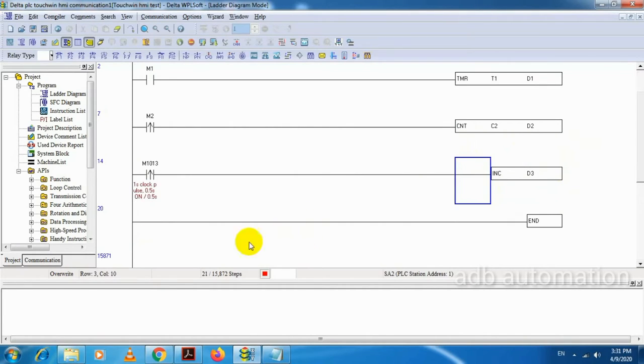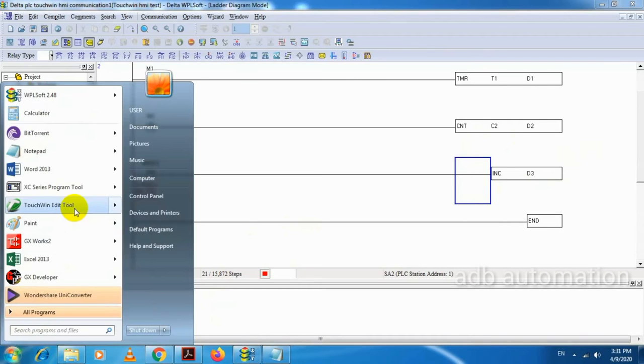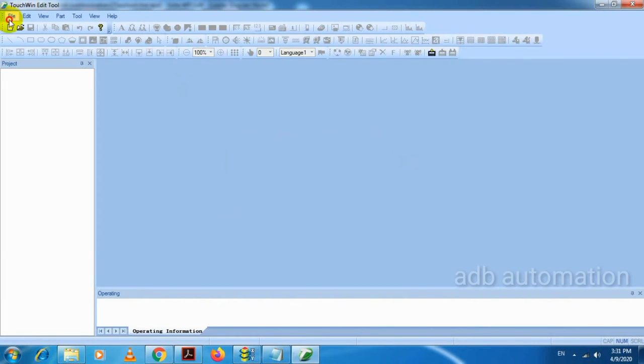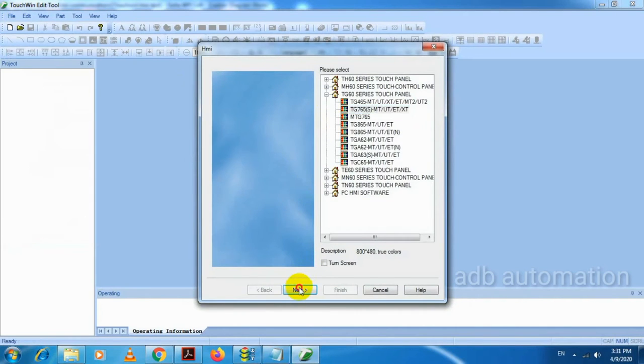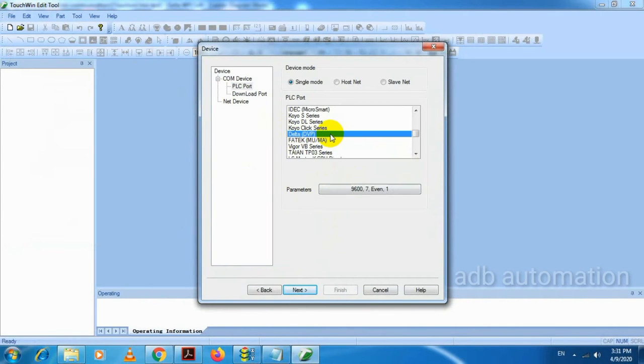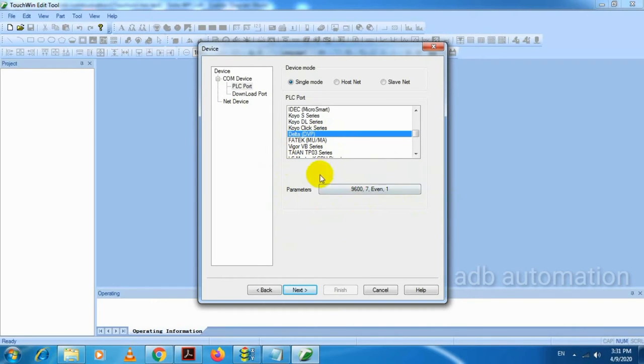Next, we will do the program in HMI. For that, I have to open the software and create a new project. Select Delta DVP series PLC. The parameters are there — no need to change these default parameters. The baud rate is 9600, data length is 7, parity is even, and stop bit is 1.